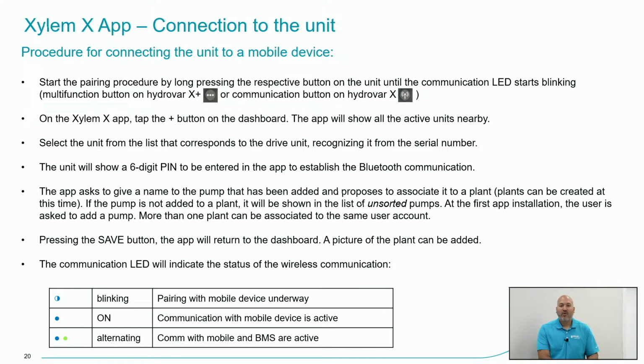You would look on the mobile phone. It should pop up any units that are in that pair mode around you. You should see a serial number. On the side of the VFD, there is a nameplate sticker that would have the serial number there. You just want to make sure it matches the one you're selecting or trying to connect to. A 6-digit PIN will show up on the Hydrovar X screen. You would type that into your mobile phone, and it will make the connection for you, and then you'll be able to operate and configure the unit through the mobile application there.